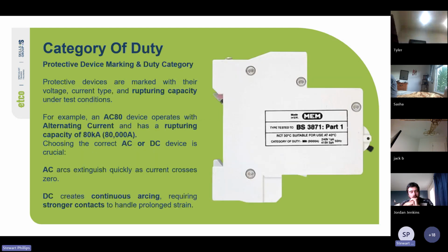Cool. So you've got your category of duty: protective devices, device marking, and duty category. Protective devices are marked with their voltage, current type, and rupturing capacity under test conditions. For example, an AC80 device operates with alternating current and has a rupturing capacity of 80 kA, or 80,000 amps. Choosing the correct AC or DC device is crucial. AC arcs extinguish quickly as current crosses zero. DC creates continuous arcing, requiring stronger contacts to handle prolonged strain. So one of the big differences between AC and DC switches is that DC switches have a comparatively larger air gap between the contacts because of that arcing.